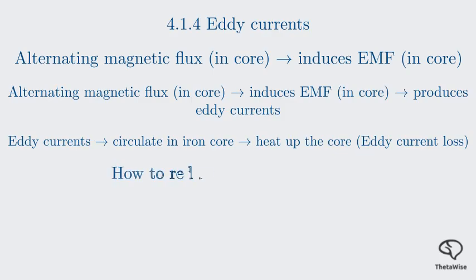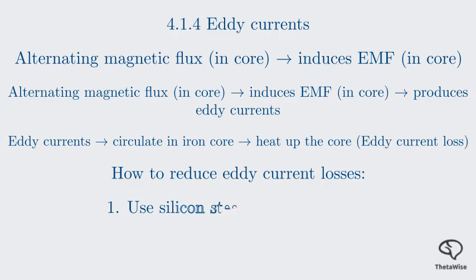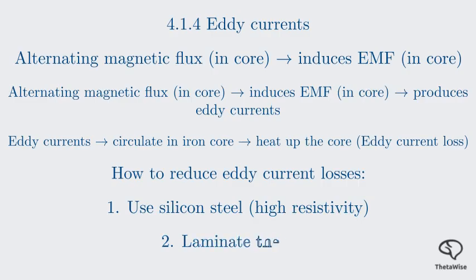To minimize these losses, manufacturers take two key steps. First, they use silicon steel, which has a higher resistivity than pure iron. Higher resistance means smaller currents. Second, and this is why we have a laminated core, they laminate the core. By dividing the core into thin, insulated sheets, we break the path for large circulating eddy currents, forcing them into much smaller, weaker loops, which significantly reduces the heat generated.